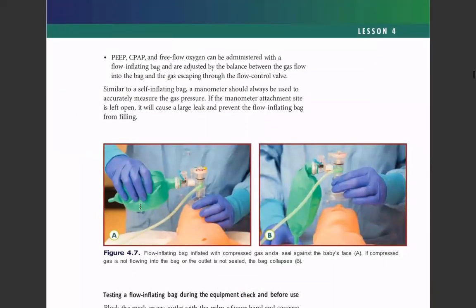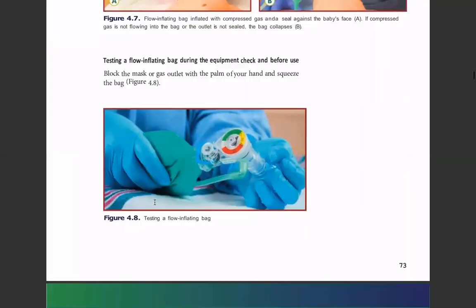This is your flow inflating bag, whatever you see in your OT, which the anesthesia fellow will be holding. This will open up only when adequate flow is coming and only when a tight seal is there. Then only this will get inflated. If there is a leak, it will not get inflated.